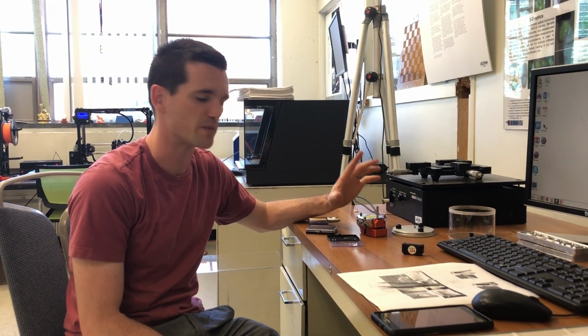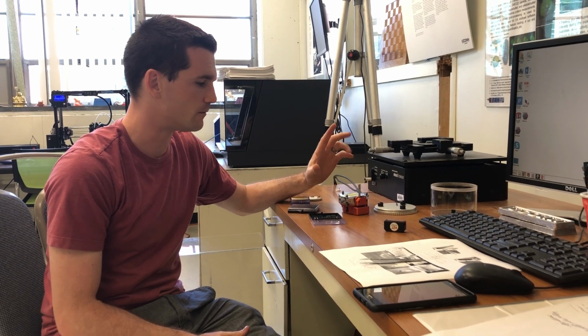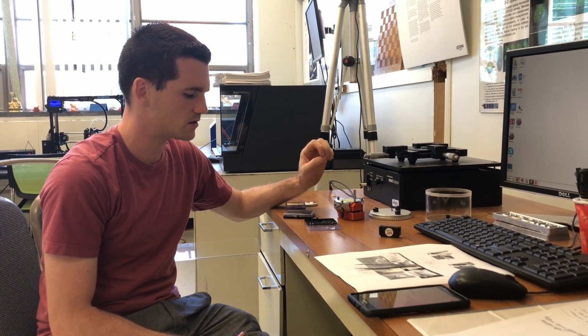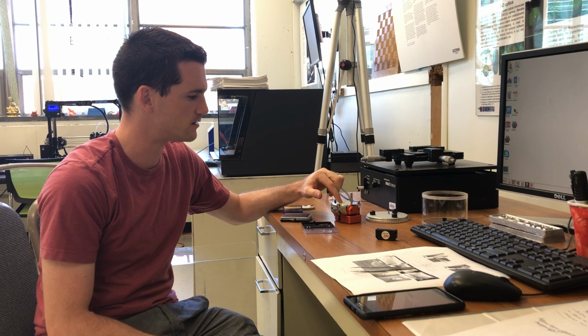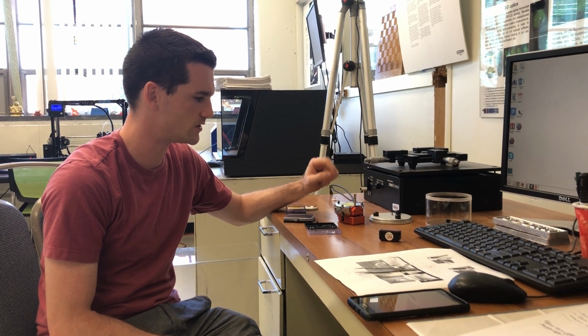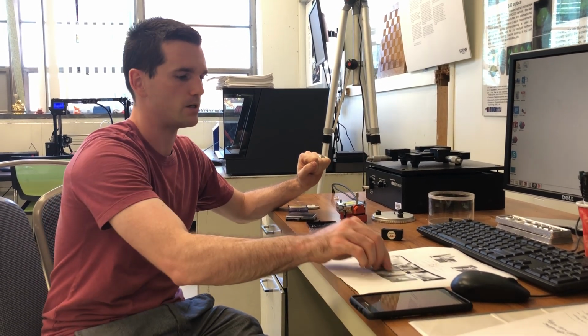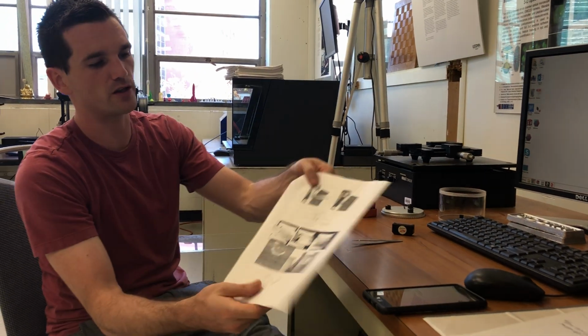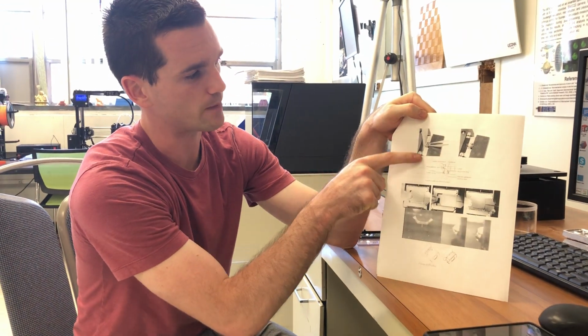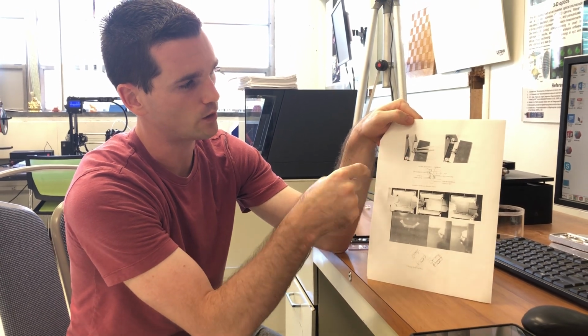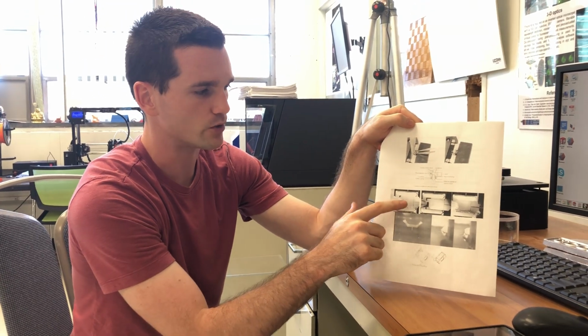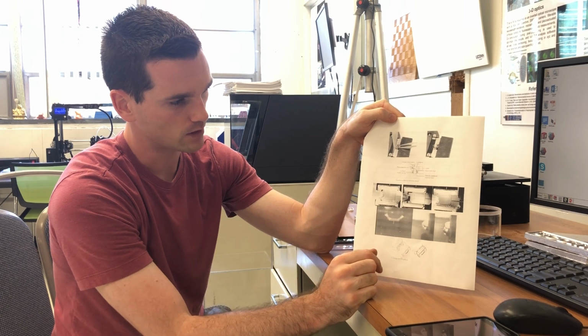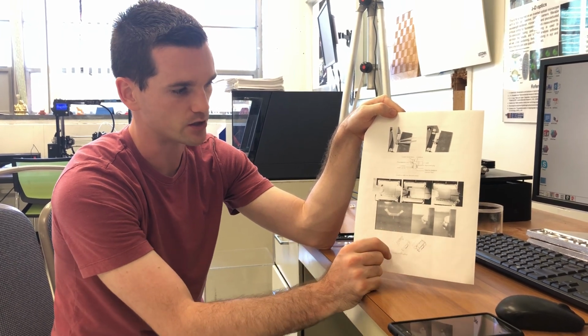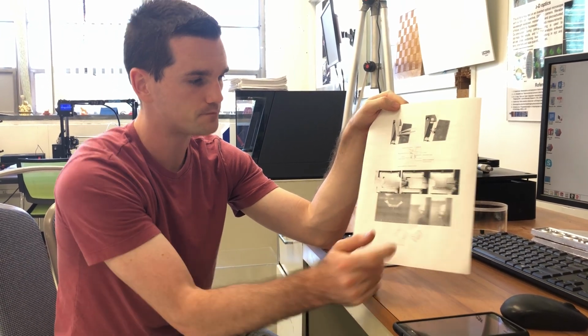This video is to show the tip exchange procedure on the atomic force microscope. This is a Nanosurf EasyScan 2 AFM. In the last page of our procedure, we've put the pictures from the instruction manual, which shows the process: putting in this pin, removing the tip, how to align the new tip, and how to do the initial testing to make sure it's working.